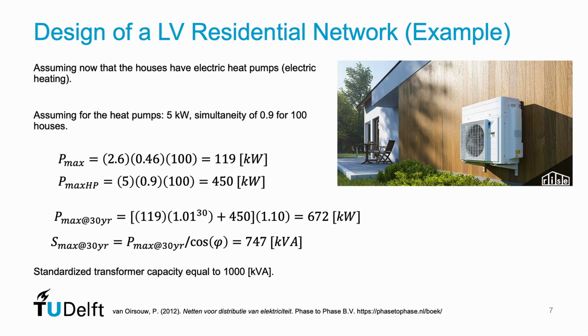If we repeat the same design calculations now considering that all houses will include a 5 kilowatt heat pump, we will reach a new estimate for the transformer of 1000 kilovolt ampere. This is the moment to pause the video to check how these calculations were done.